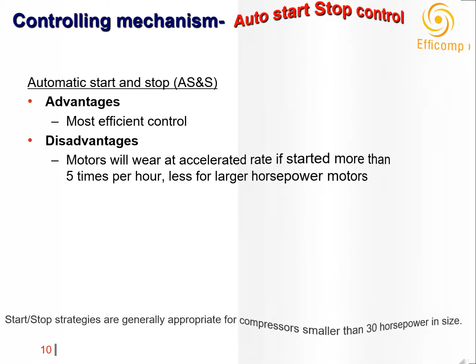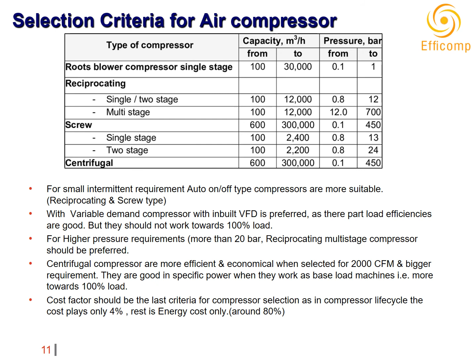For small intermittent requirements, auto on-off type compressors are more suitable, mainly for reciprocating and screw types. With variable demand, compressors with inbuilt VFD are preferred as their part load efficiencies are good, but they should not work towards 100% load. For higher pressure requirements, that is more than 20 bar, reciprocating multi-stage compressors should be preferred. Centrifugal compressors are more efficient and economical when selected for 2000 CFM and bigger requirements. They are good in specific power when they work as base load machines, that is more towards 100% load. Cost factor should be the last criterion for compressor selection, as in compressor life cycle cost it plays only 4%, the rest is energy cost, around 80%.